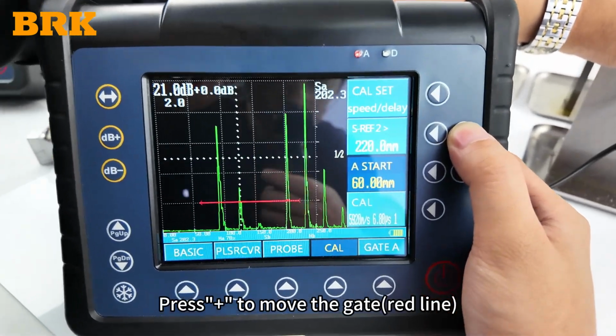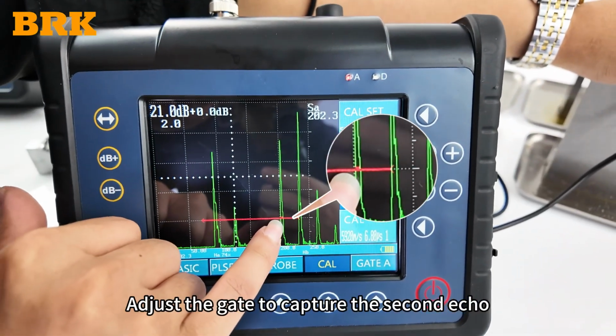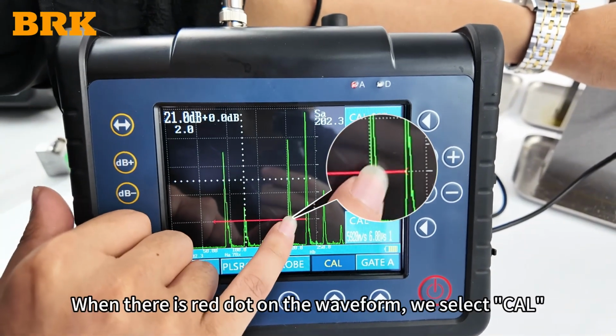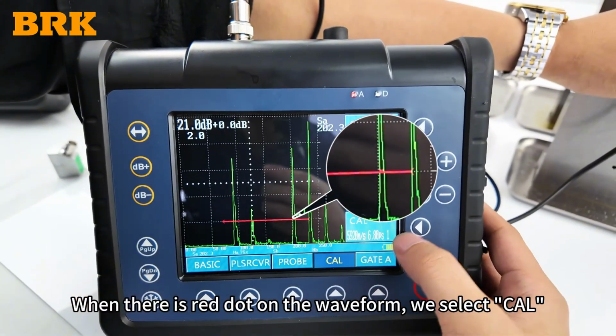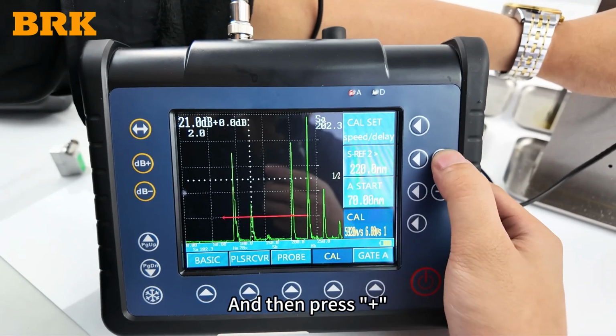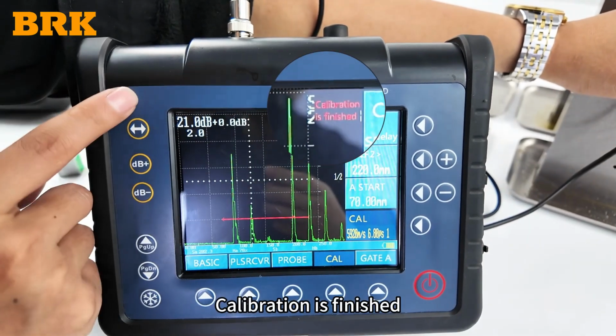Press plus to move the gate red line. Adjust the gate to capture the second echo. When there is red dot on the waveform, we select Cal. And then press plus. Calibration is finished.